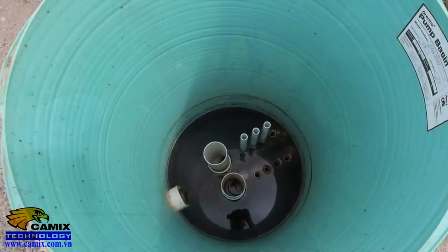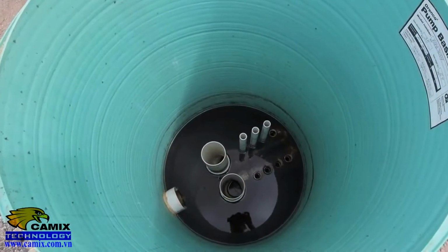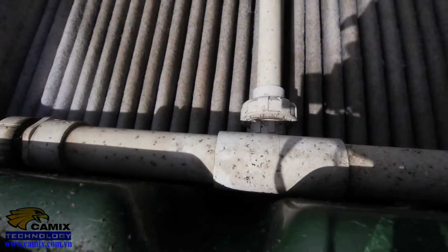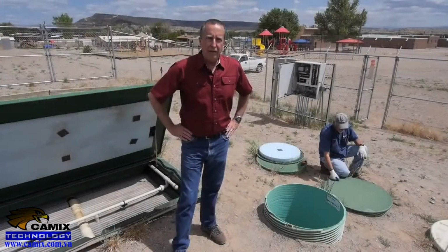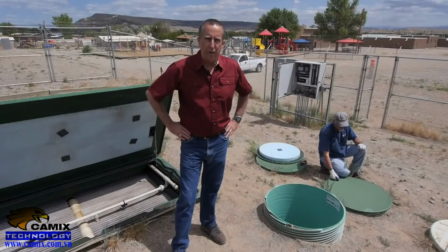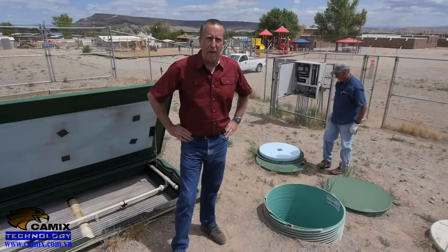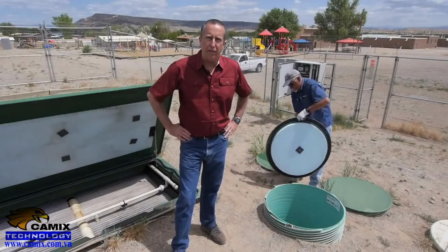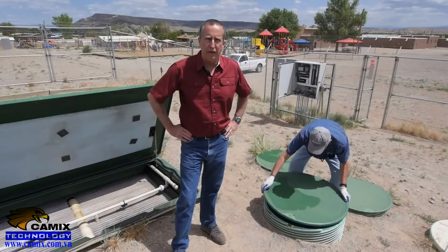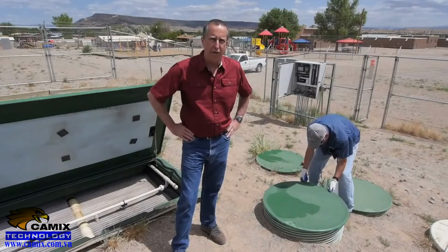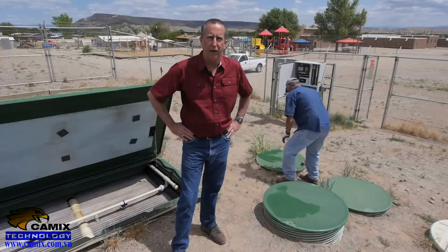Over in this other side, we've got the recirculation going on. This is how the system keeps itself healthy, keeps this fabric moist even when there's no flow coming in, as it is constantly going around and around. These on-site treatment systems are a little bit more sensitive than a large regional treatment system. Since the population of biomass is fairly small at these systems, they can be poisoned by chemicals that might be improperly discharged into the sewer, things like cleaners, pesticides, herbicides, household chemicals, industrial solvents can knock these smaller systems offline.